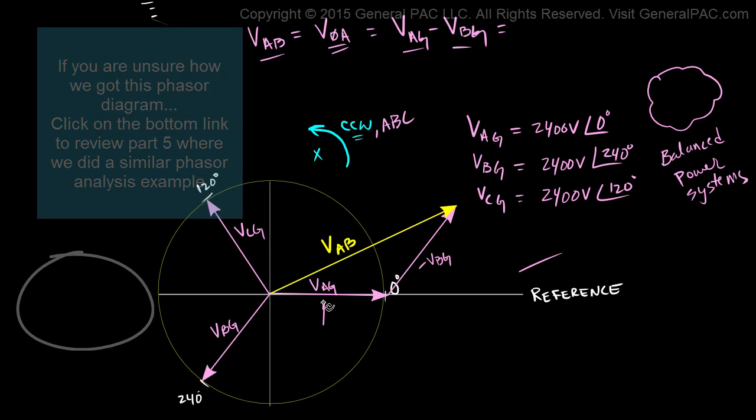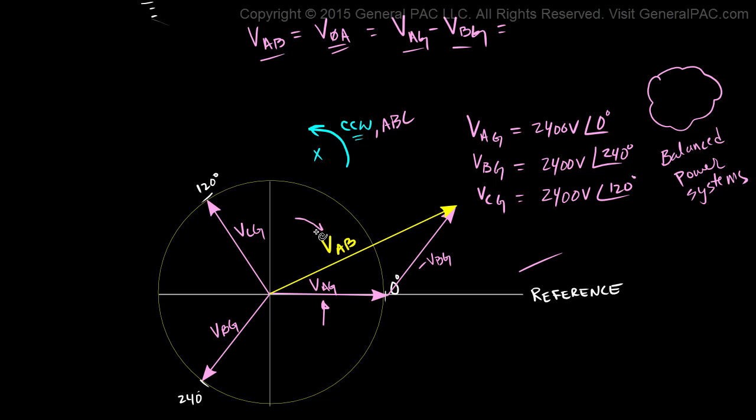Now that we have this visual representation, if we were to relate Vag to Vab, what would we have to do? We would have to shift Vag by 30 degrees in the counter-clockwise direction. And then we would have to multiply it or stretch it by 1.73 or the square root of 3 so it lines up with Vab.